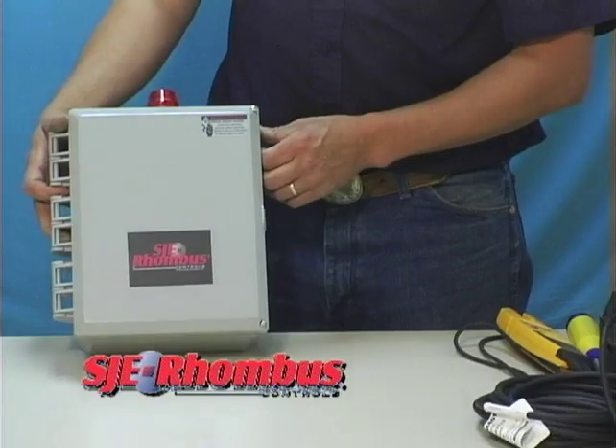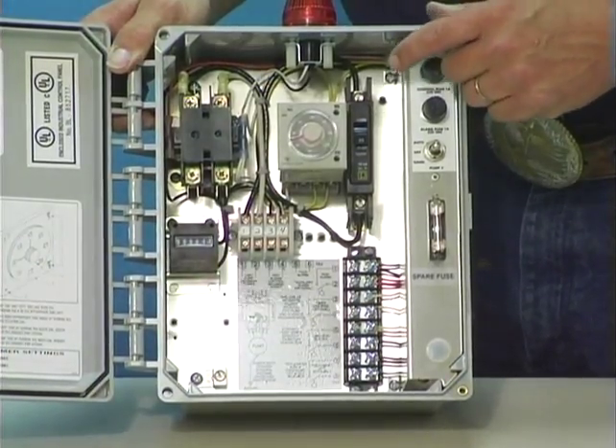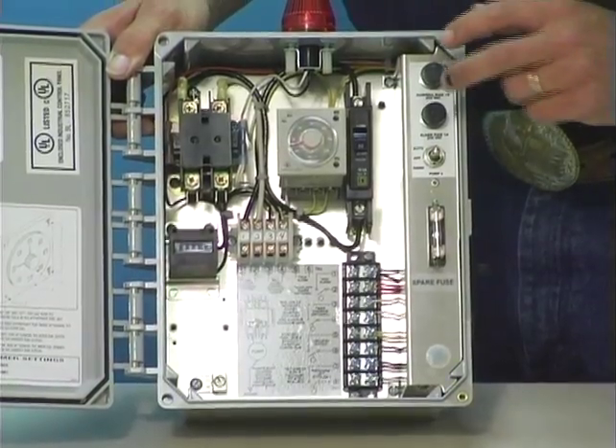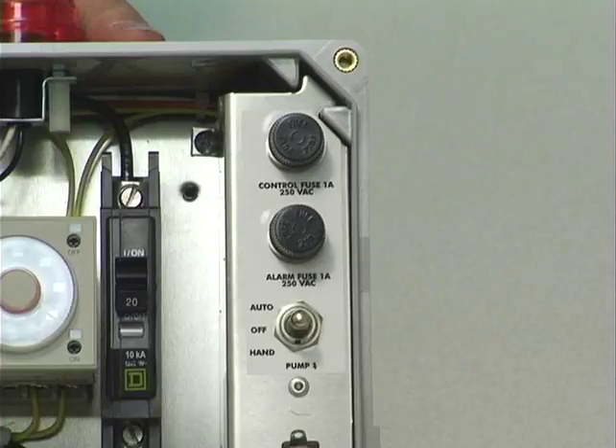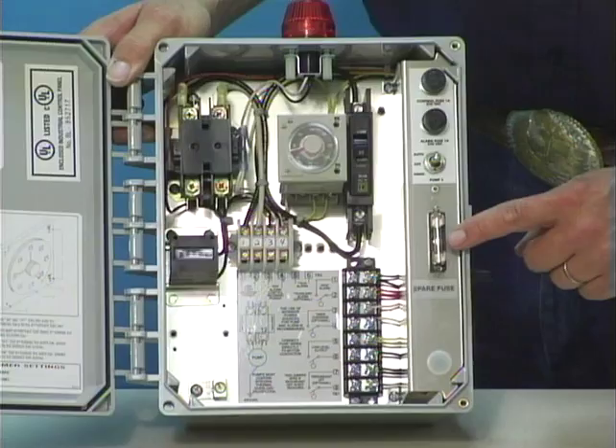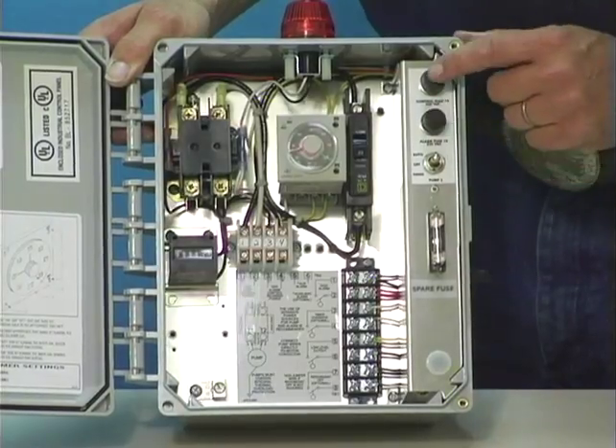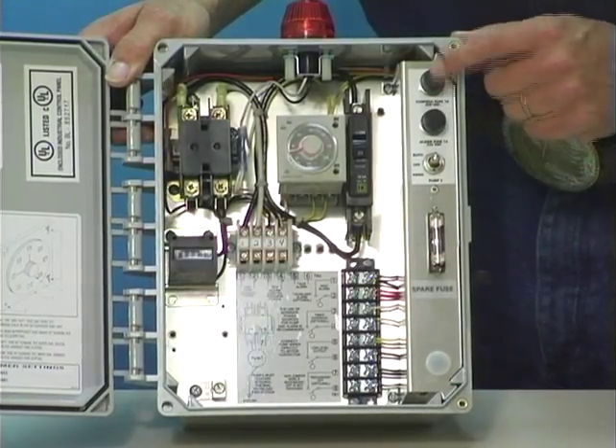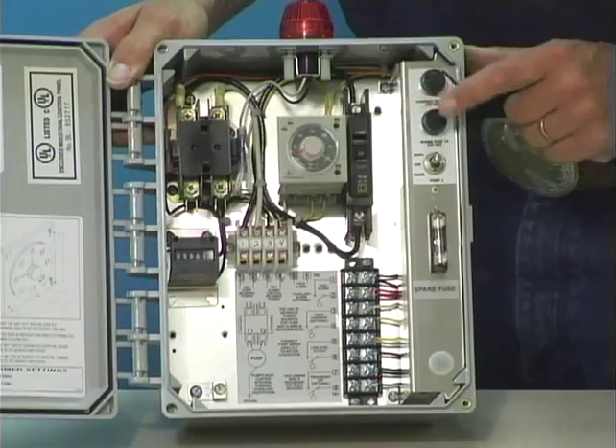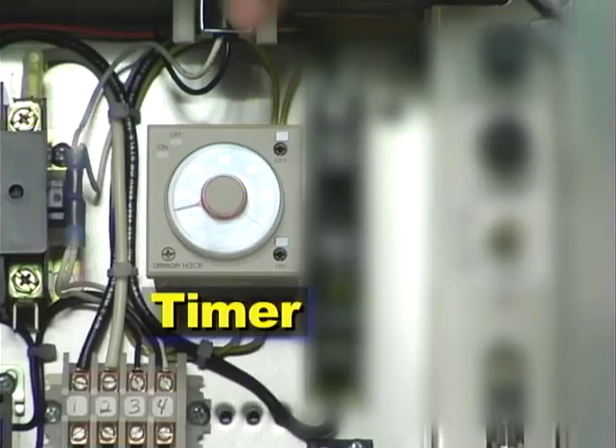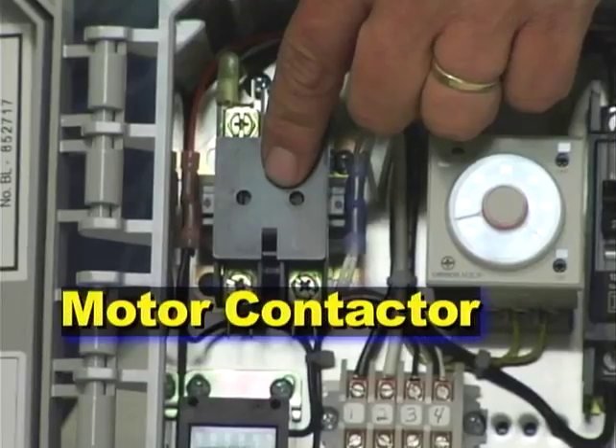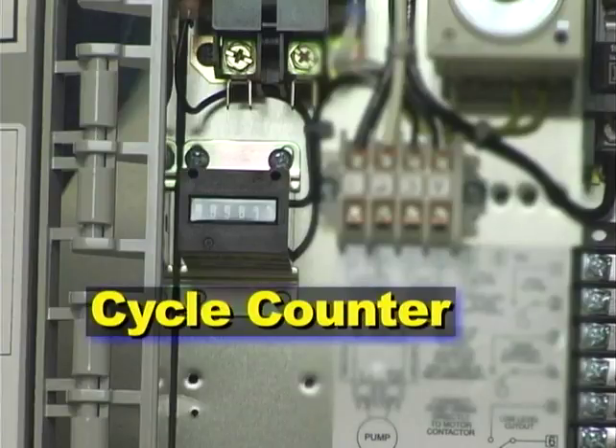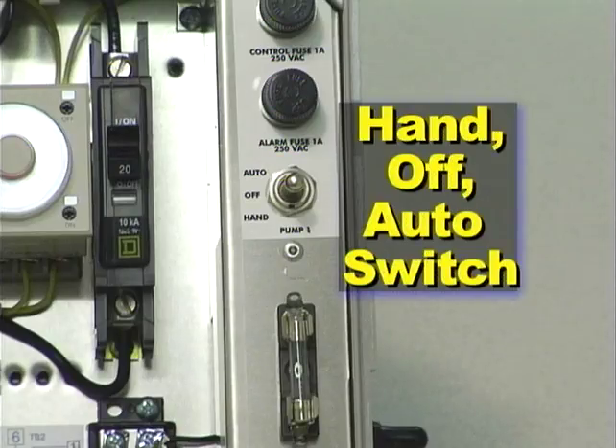This happens to be another control panel, the SJE Rhombus. Pretty much all the same components on this control panel as with the Orencos. The only thing different is, instead of circuit breakers, Rhombus uses fuses, which are underneath these covers. They look just like these spade type, and they will act as the circuit breakers. It does have a control circuit breaker for the controls. These are the breakers for the alarm functions. Has the same timer, has a motor contactor, has a cycle counter. It also has a hand-off auto switch.